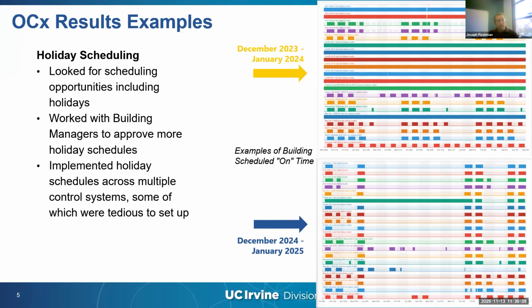So some of the examples of results is holiday scheduling. So we look for some scheduling opportunities during the holidays. As you can see in the top right, in the 23-24 holiday season, we had a lot of air handlers that were running 24/7, even though the campus really shuts down from about December 15th until after the first of the year. So one of the things that I did was to work with the building managers to approve more holiday schedules, make sure that the buildings that we thought could be scheduled would be acceptable to the building to also be scheduled. And when we got that approval, we went ahead and implemented these holiday schedules. And you can see in the bottom right how almost every building, in this set of charts, is now scheduled. And so that's just basically free energy savings.